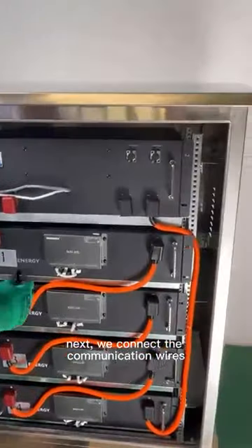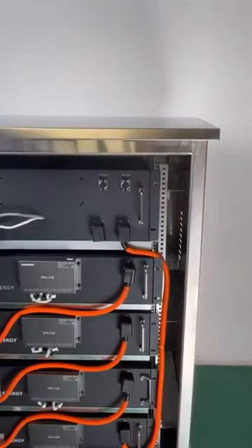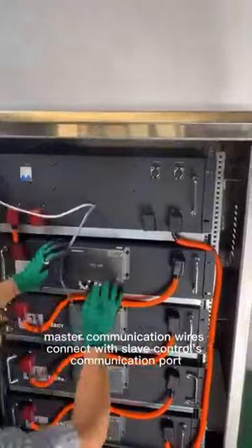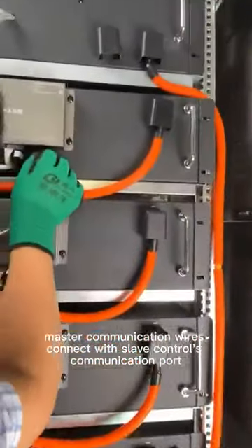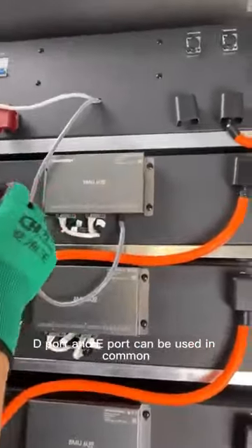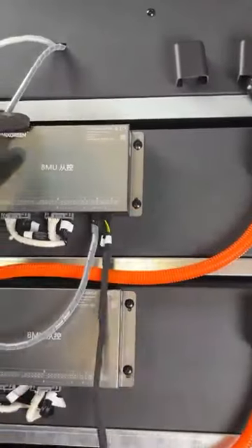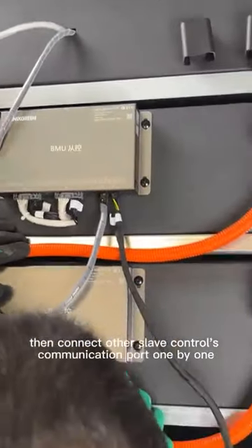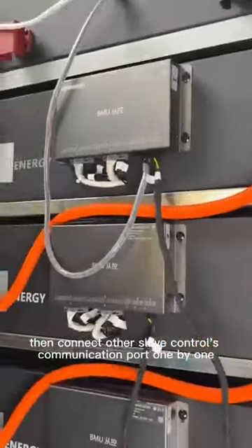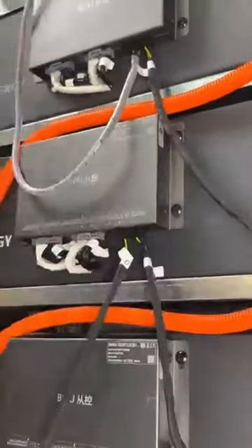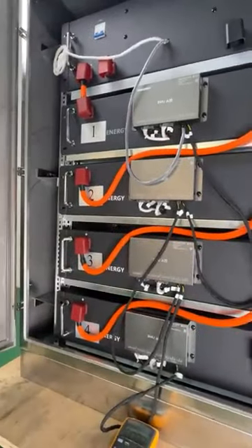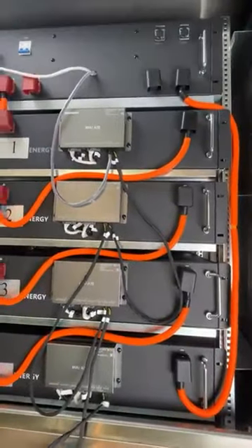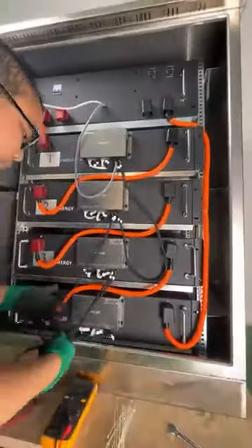Next, we connect the communication wires. Master communication wires connect with slave controls communication port. D port and E port can be used in common. Then connect other slave controls communication ports one by one. Sort out the wires.